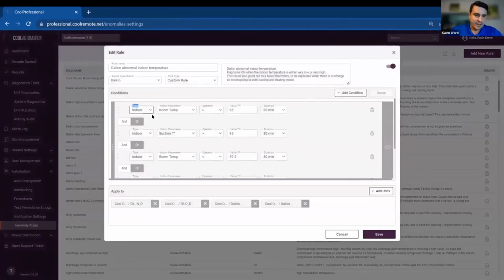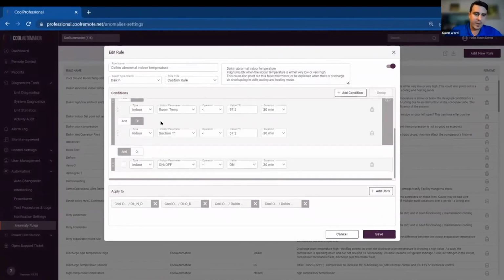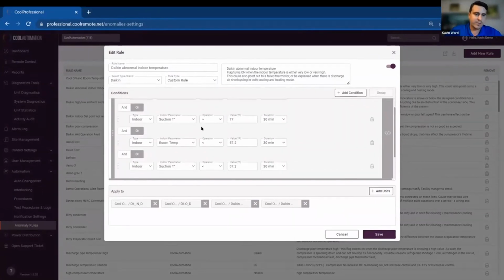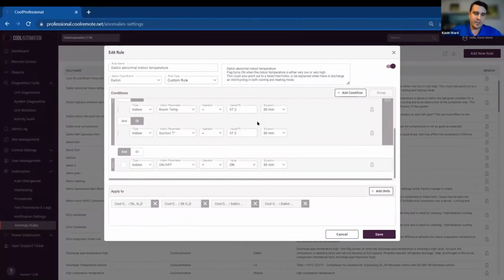So we can actively set this alert to monitor the room temperature or the suction temperature of that indoor unit. This value is completely customizable, so we can have it a little bit tighter of a range, maybe 77 degrees, and then it will be monitoring that for a certain length of time. But anytime the room temp is above 77 degrees, or if the room temp falls below a certain value, this anomaly rule will trigger an active alert to your email or via text, and you'll instantly be alerted that there's something wrong or something that is consuming more energy than it should in the space.